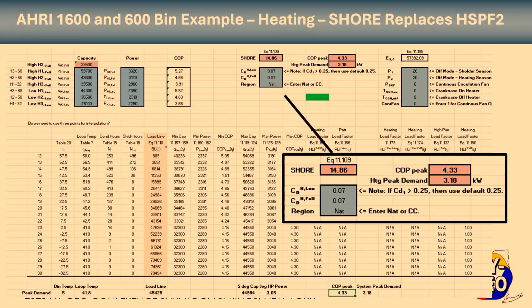Now, if you're familiar with 210, 240 and how a SEER is calculated, you don't need to see these numbers, but I'm just showing you the spreadsheet so you kind of get a feel for it. If you run a test, like this is a cooling test here, or a heating test, sorry, here. So you would run your heating tests at like several points, and then you plug them in, and the bin method here for the DOE Region 4 is typically what it used to be, will actually calculate your SEER and HSPF, right? You're probably used to, maybe most of you have seen that kind of calculation.